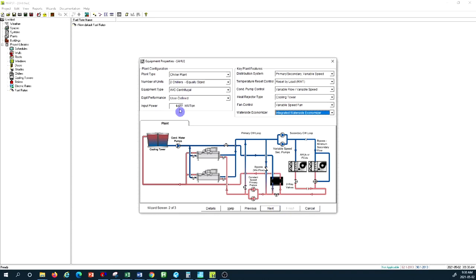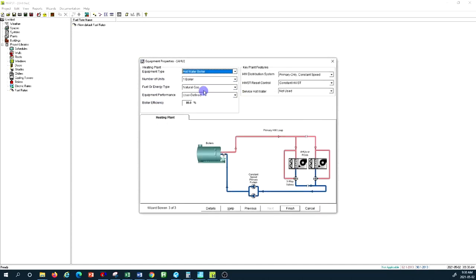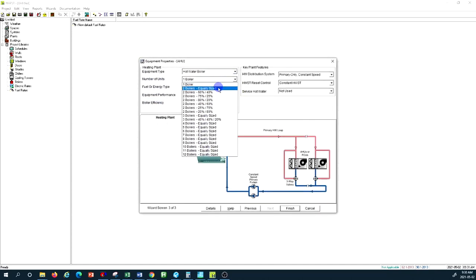I've selected the quantity of chillers and configured the system. There is a primary loop and a secondary loop that takes the chilled water to the air handling units. For the hot water plant, I select one to two equally-sized boilers running on natural gas, with efficiency set to 95 percent for condensing boilers.